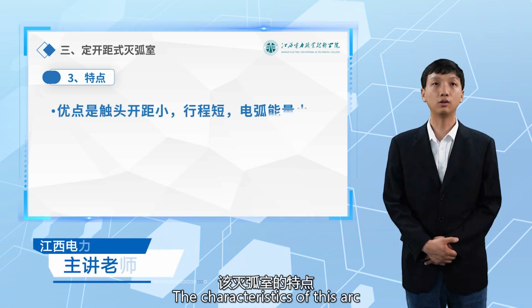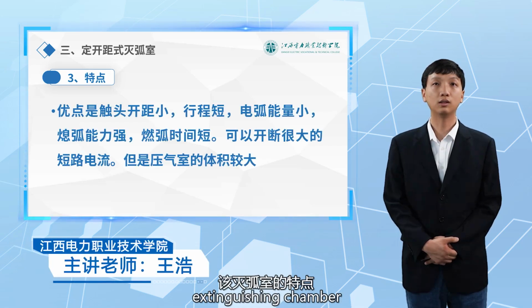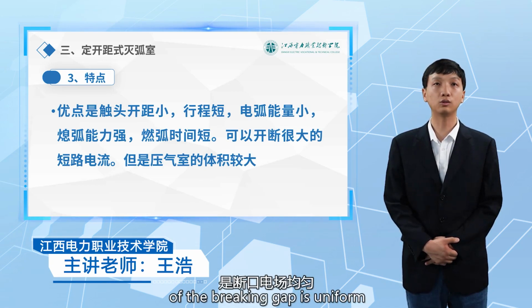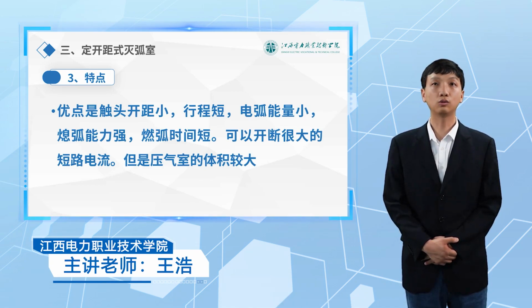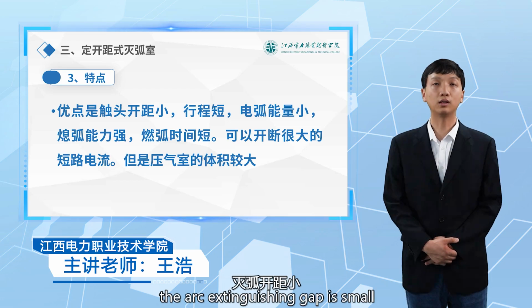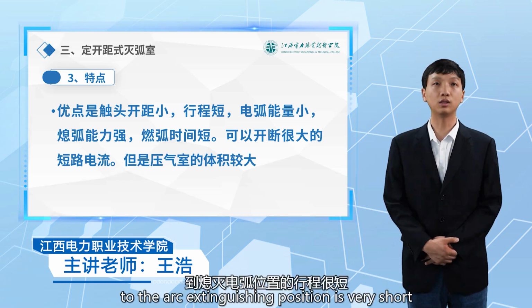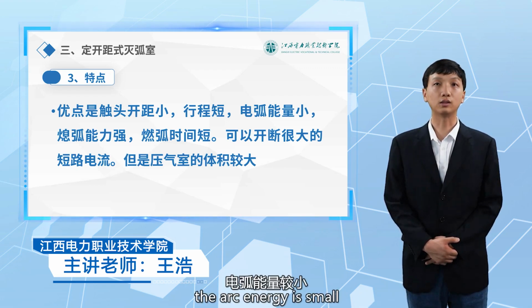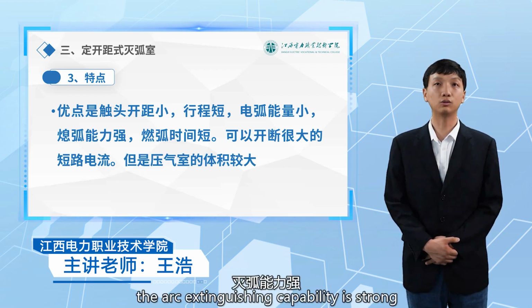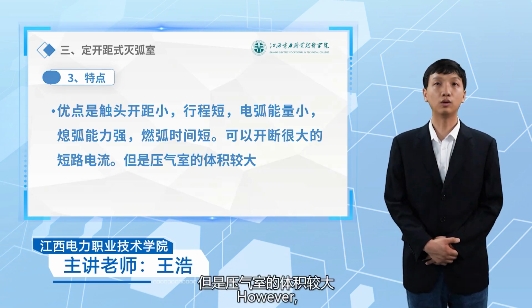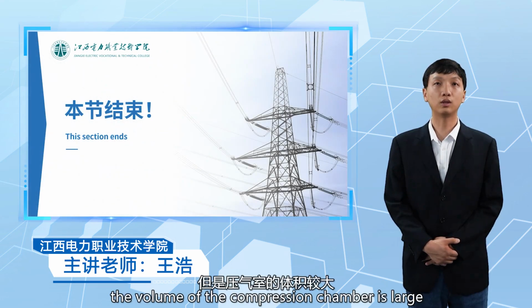The characteristics of this arc extinguishing chamber are that the electric field of the breaking gap is uniform. The arc extinguishing gap is small. The arc extinguishing position is very short. The arc energy is small. The arc extinguishing capability is strong. However, the volume of the compression chamber is large.